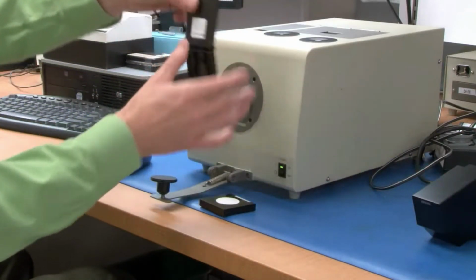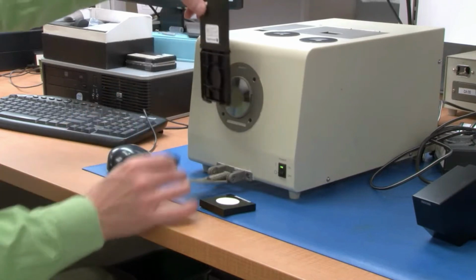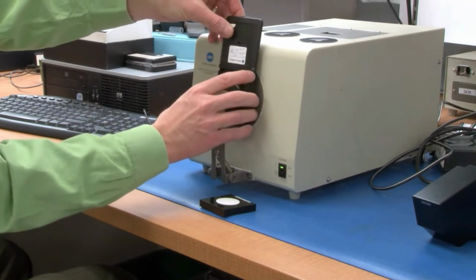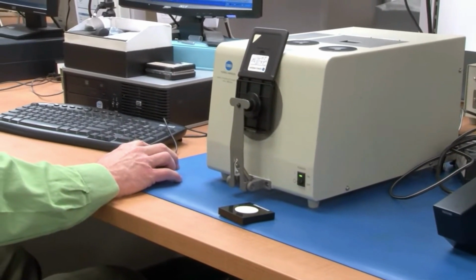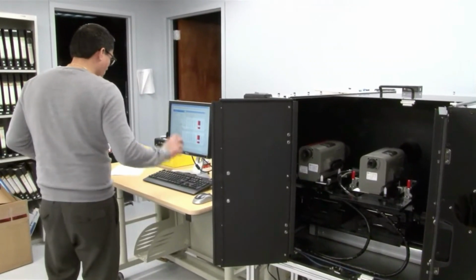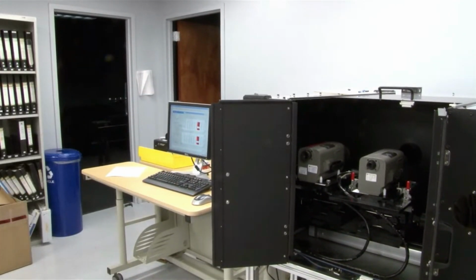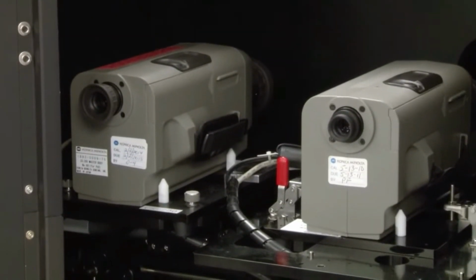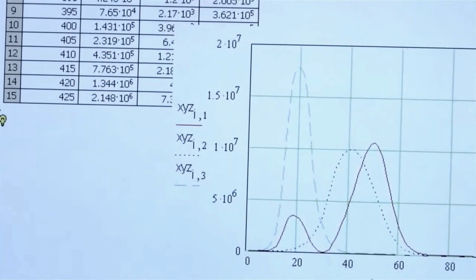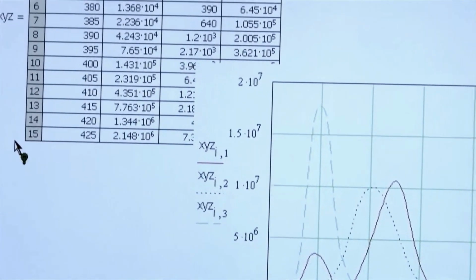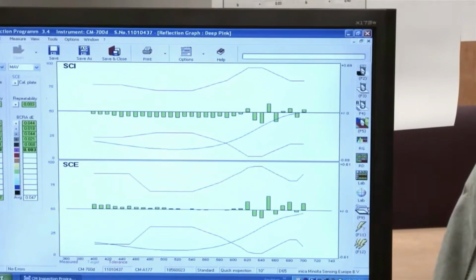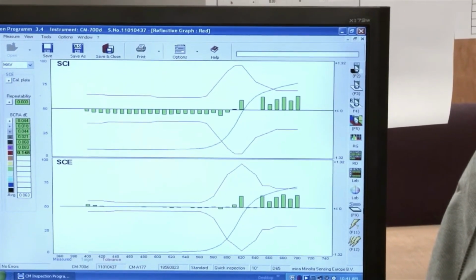Our white tile is calibrated to NIST. NIST is the National Institute of Standards and Technology, and most standards in the U.S. are calibrated to a NIST standard. So you would send it back so that you would know that the instrument is calibrated properly to the master database and NIST white. It is important to calibrate and monitor your measurement equipment on a regular basis to minimize the risk of improper measurements or instrument failure. Inconsistent measurement values translate directly to inconsistent products and can cost a company hundreds of thousands of dollars.